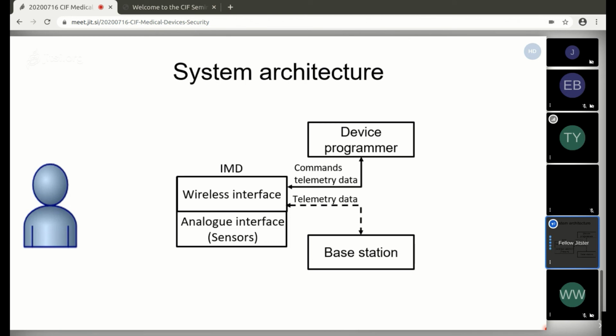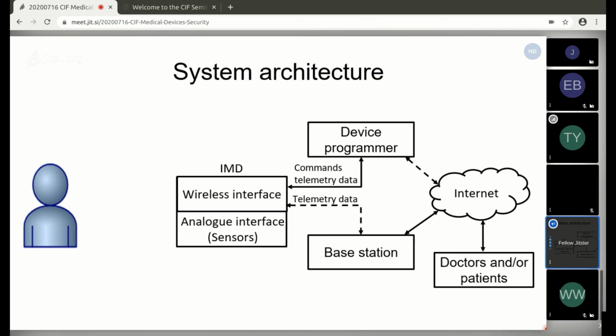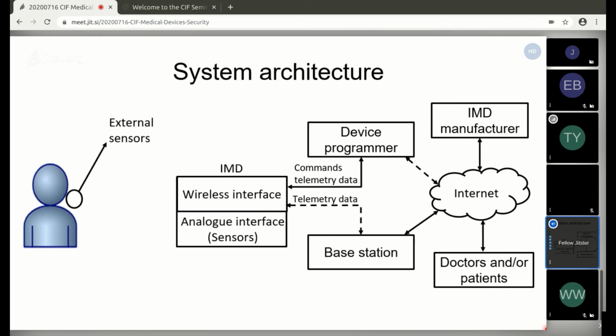Doctors, and in some cases also patients, can then sometimes access a web portal to review the telemetry data that was collected by the base station. Typically, both the device programmers and the base stations have an internet connection that also allows the manufacturer to update the software of the devices remotely. And then another type of device that can also interact with implantable medical devices are sensors. Some of these sensors can be worn by the patients. What they do is measure several physiological signals of the patients, and then they send this information to the implantable medical device.